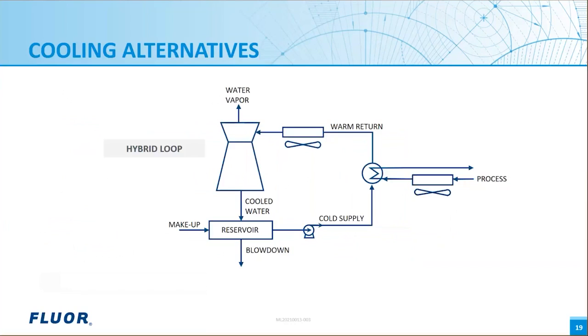A hybrid loop shifts heat rejection directly to the air and therefore minimizes evaporation. This may be practical in areas that are water constrained, but the trade-off will be against cost. For water and waste minimization concerns, with this or the open cooling loop method from the first slide, we can minimize makeup and blowdown by using a membrane system to remove hardness or other impurities that cause scale, and returning the permeate to the cooling tower.